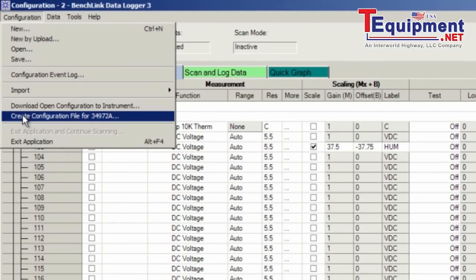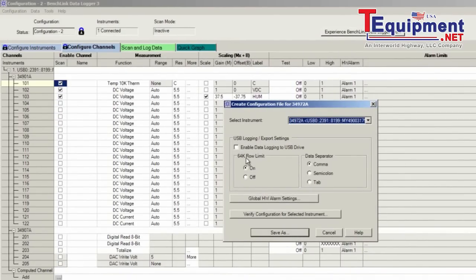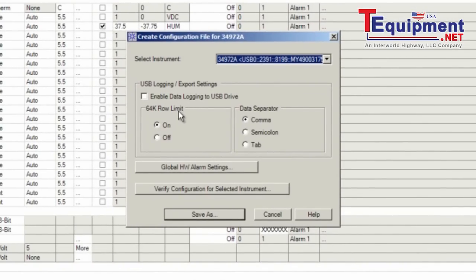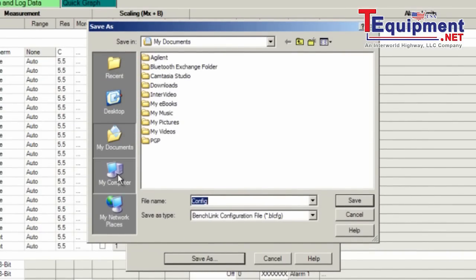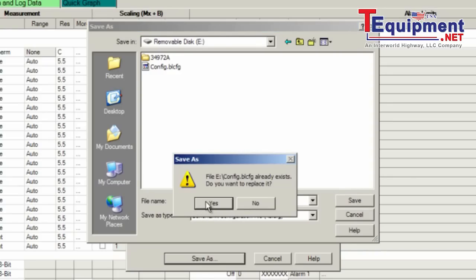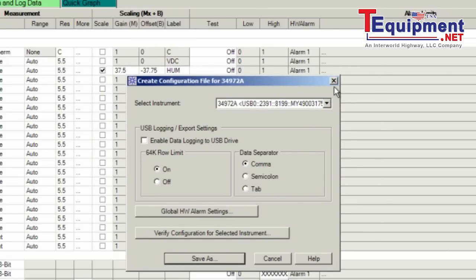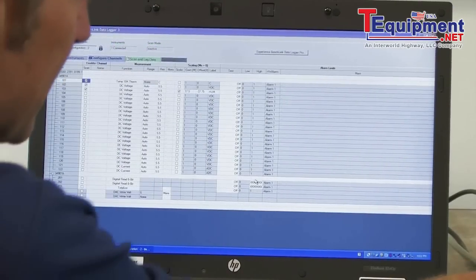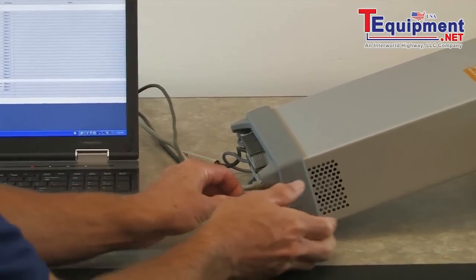Let's go ahead and save the configuration that we've set up on our BenchLink DataLogger software — I'm going to create a configuration file. It's asking about the format we can save the data to the USB stick once it's plugged into the 34972. It has the capability of breaking the file into smaller pieces if you go over 64K rows, which was important for older versions of Excel that could only take a file size of 64K or less. We also get to set our delimiter — I'm going to choose comma separated, which is good for Excel. Now I'm going to save my configuration file to the USB stick.